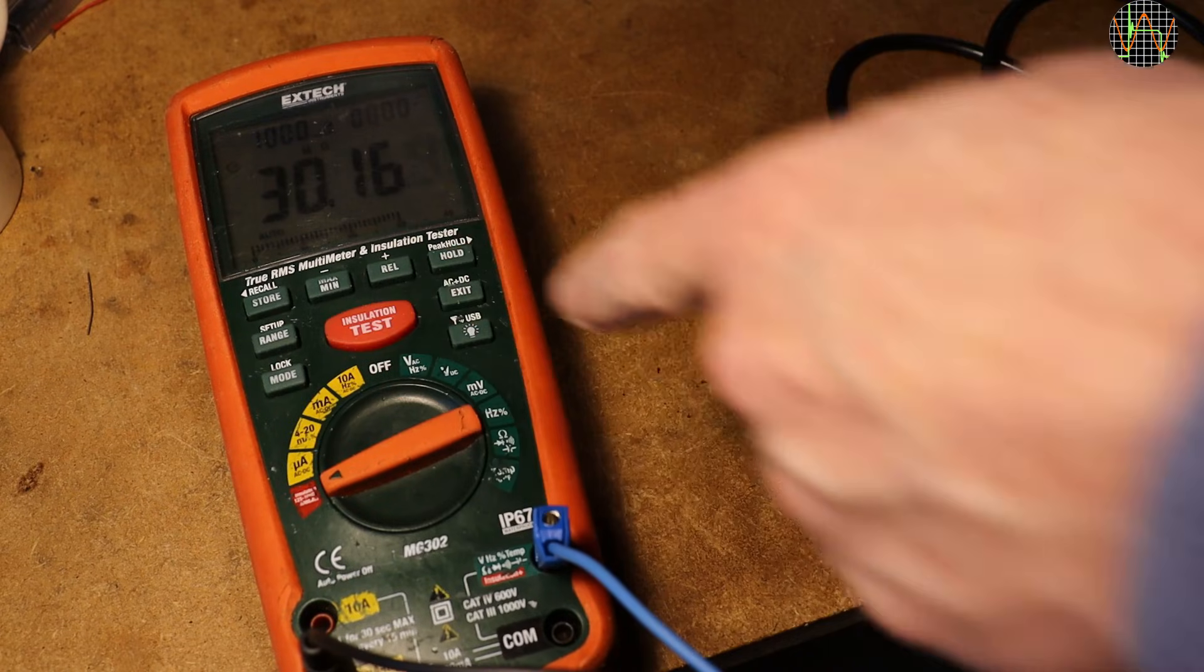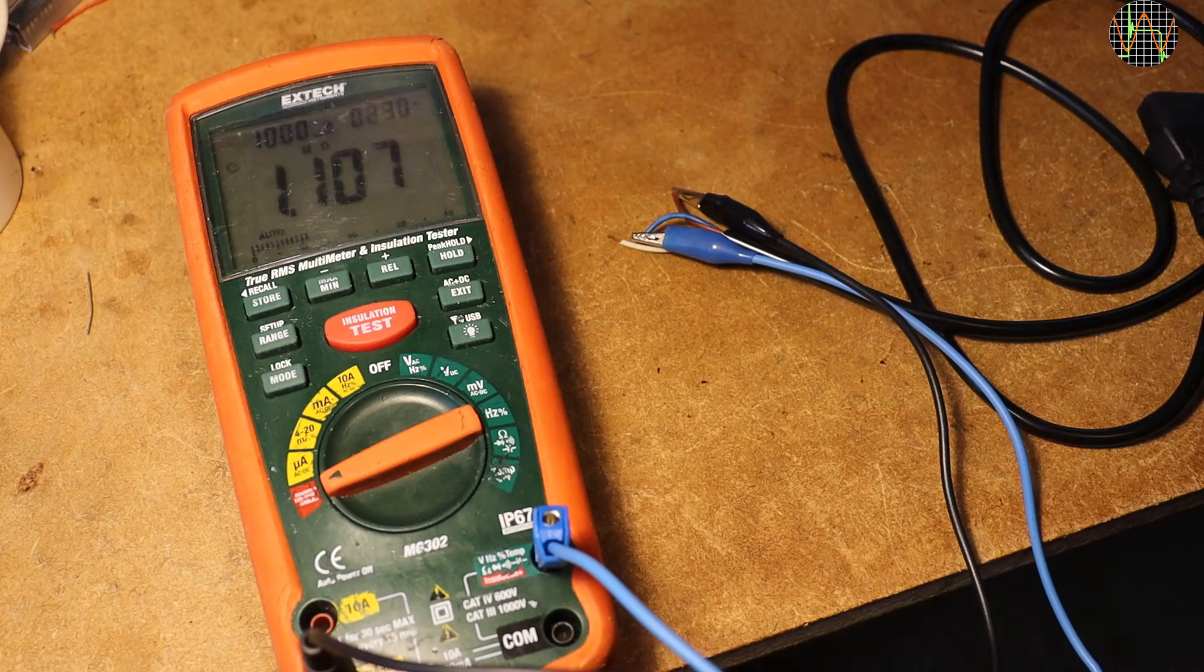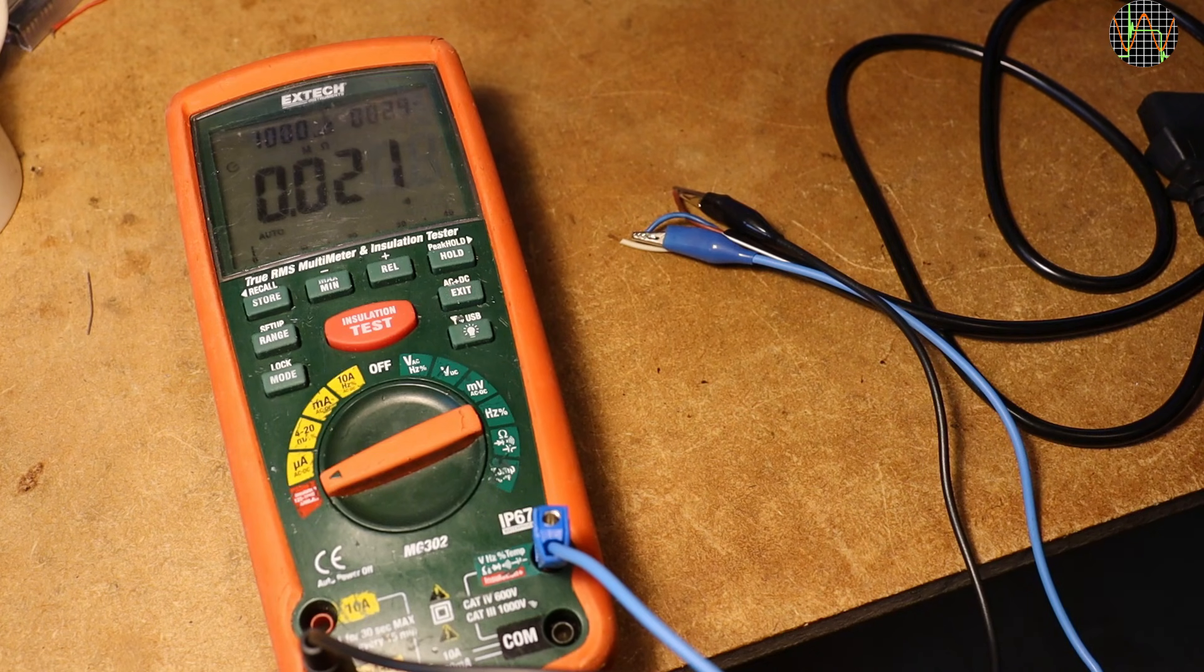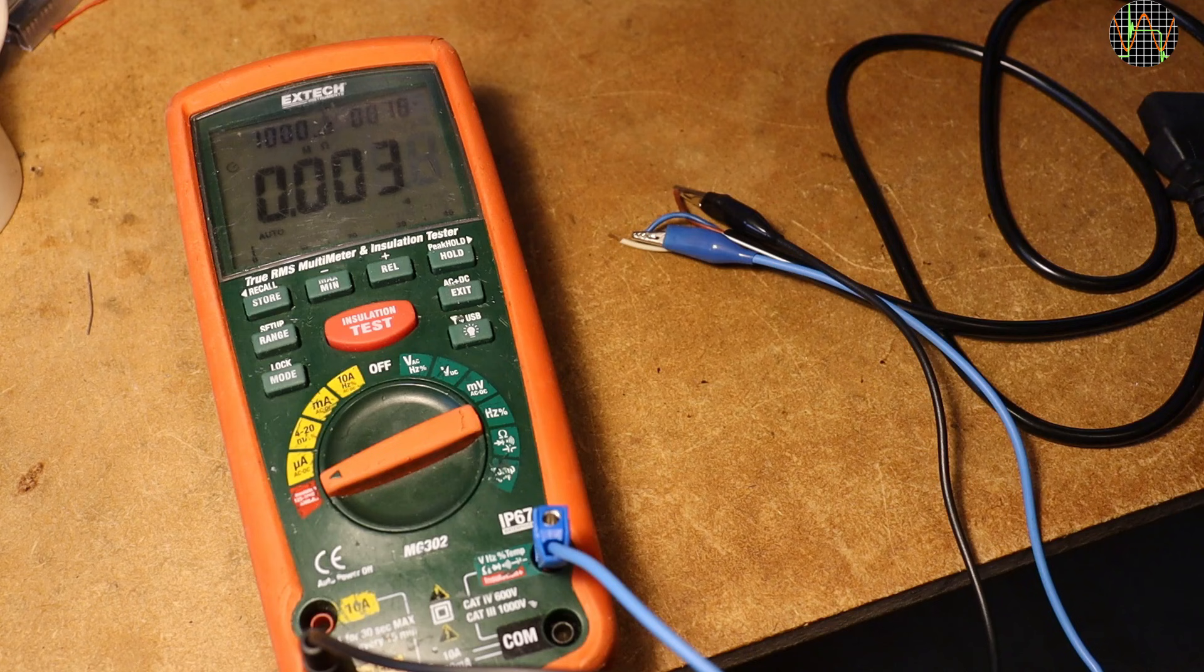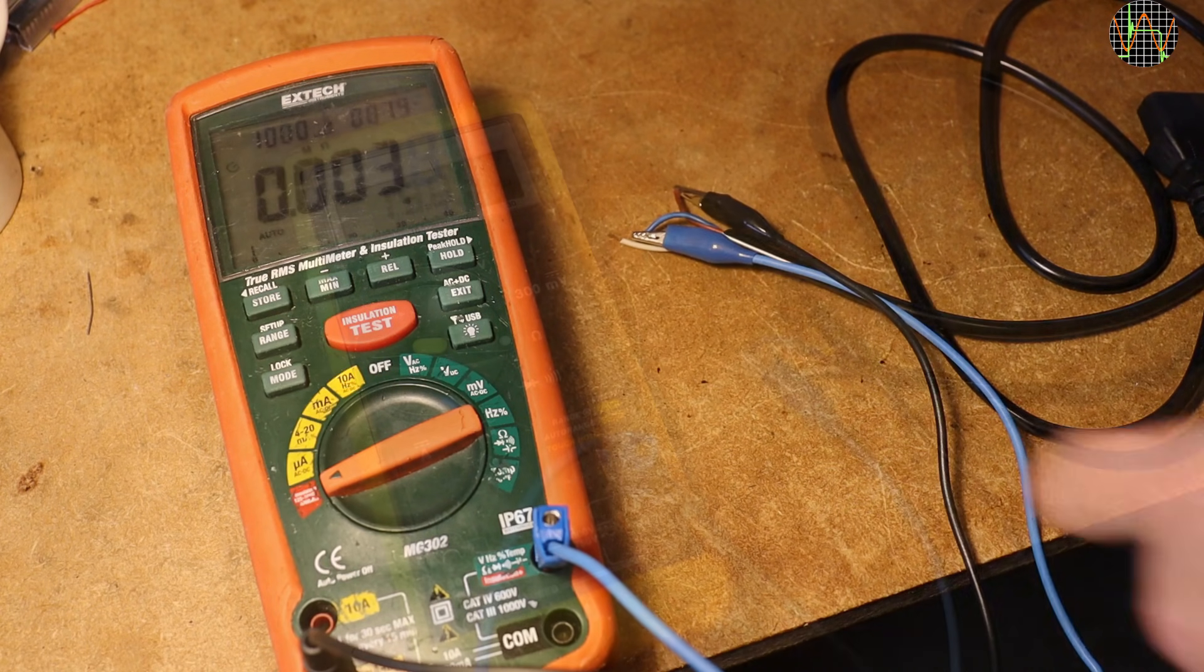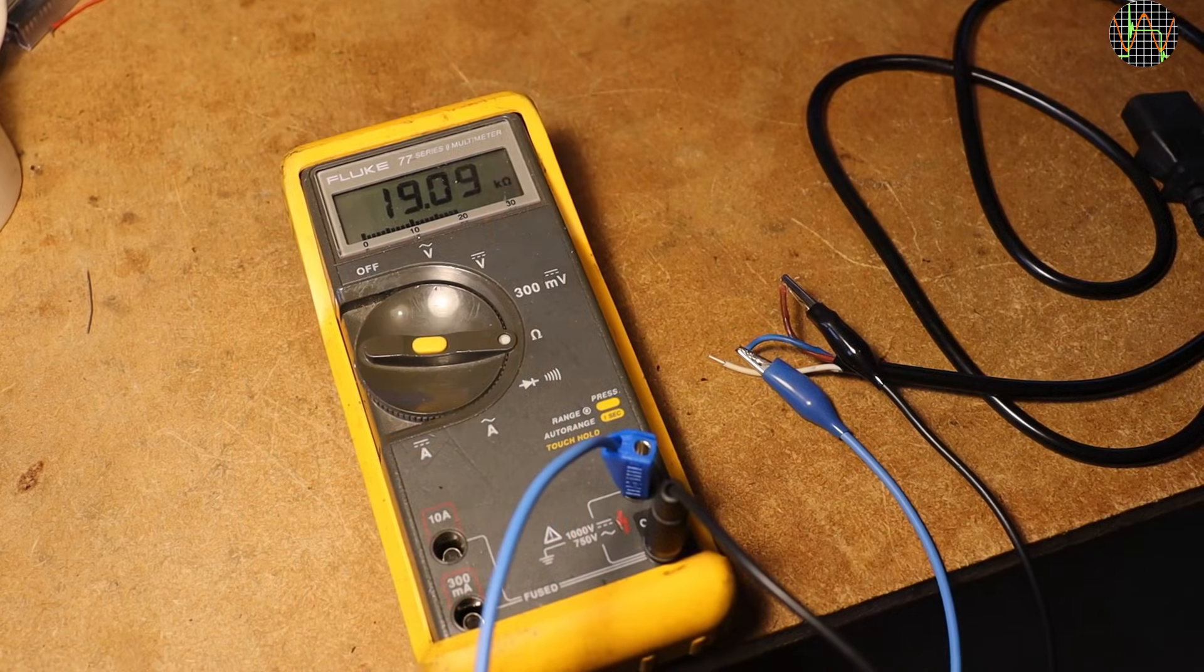Just for fun, I repeated the Extech 1000V test on the cable after it had flashed over. Sure enough, the resistance is so low that the Extech in insulation mode can hardly measure it. A more accurate low voltage reading says it is now 19 kΩ.